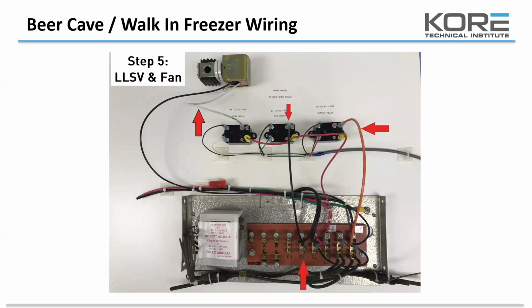This photo is showing that I took a Y wire that I had here that goes up to complete the circuit for the solenoid valve, and that is coming off the terminal number 5. In the middle one, you'll see that that particular wire off of number 5 goes down to F2, which is the other side of the fan motor to complete that circuit. And the orange wire on number 2 is going down to H2, which is the other side of the heaters. And that provides that our relays are now switching each of those components on and off.